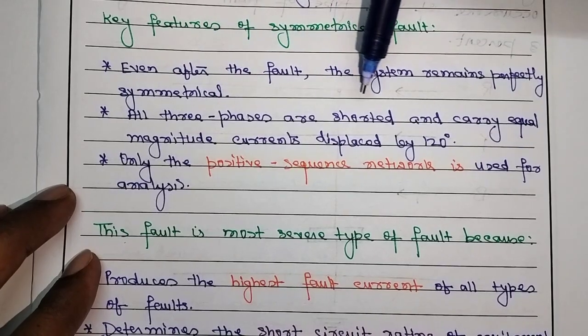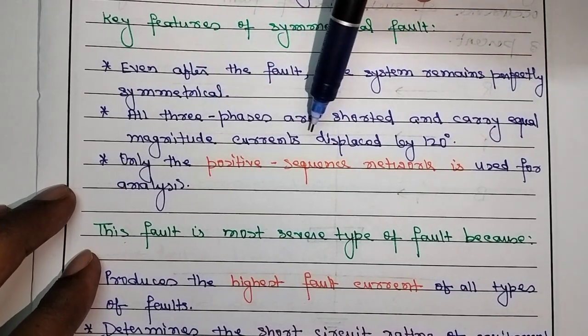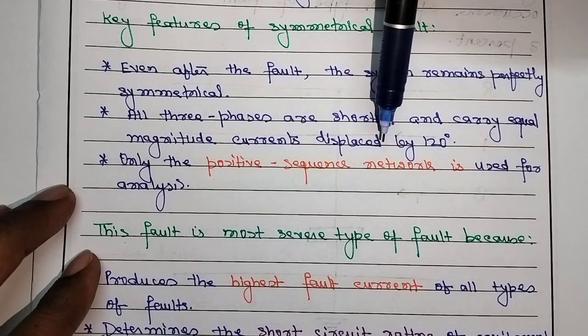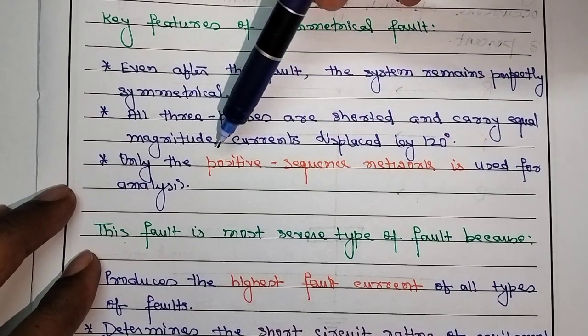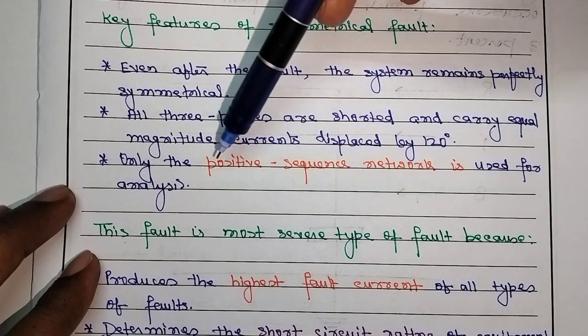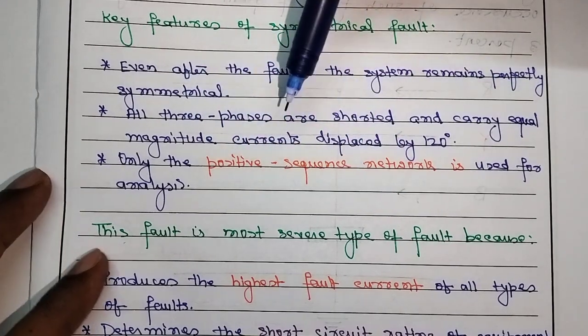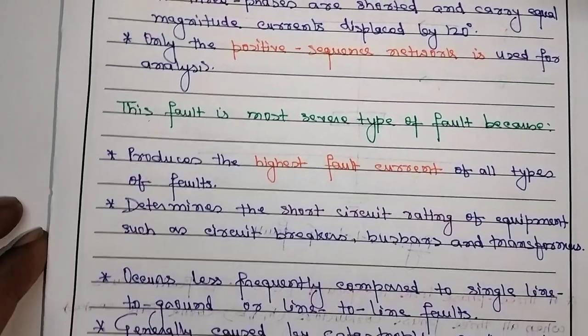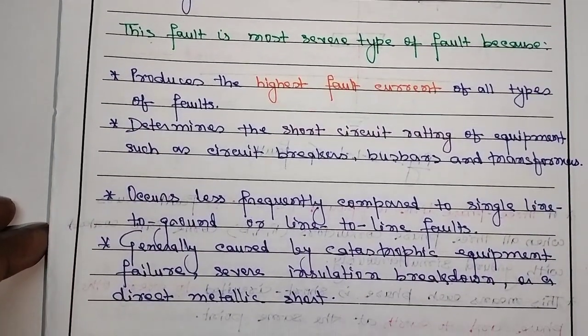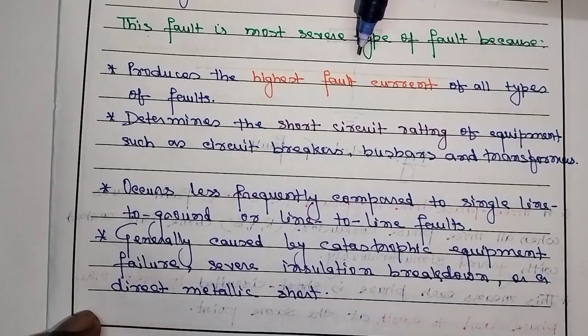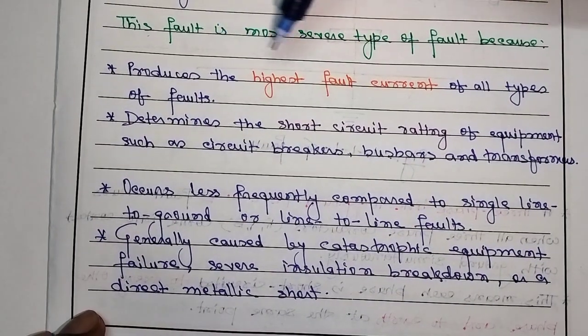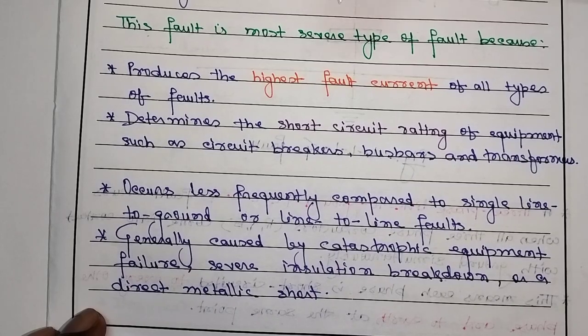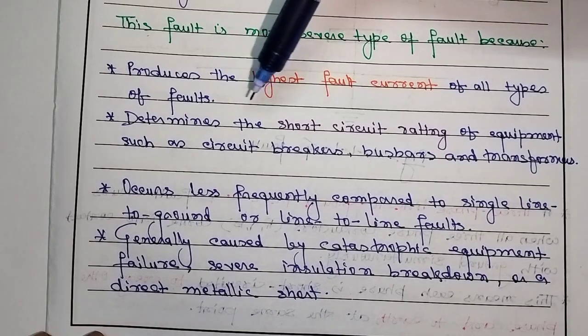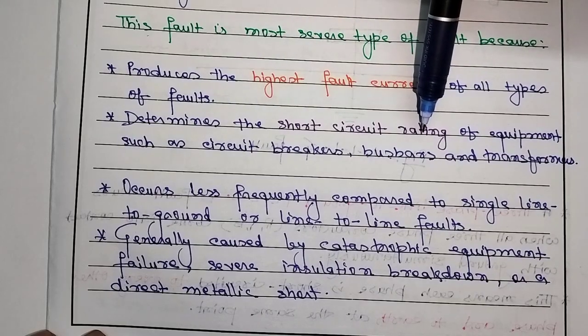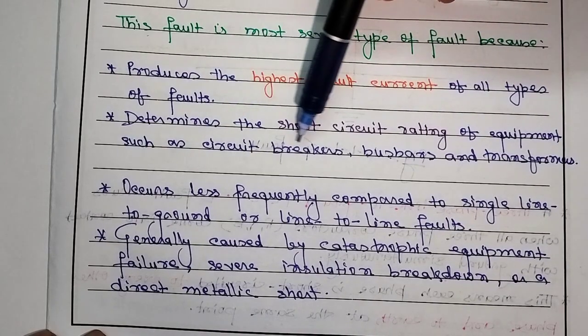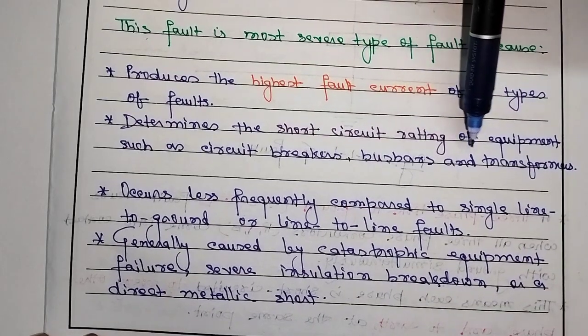All three phases are shorted and carry equal magnitude current displaced by 120 degrees. Only the positive sequence network is used for the analysis of this type of fault. Next, the fault is the most severe type because it produces the highest fault current of all the types of faults, compared to any type of fault. Next, it determines the short circuit rating of equipment such as circuit breakers, bus bars and transformers.